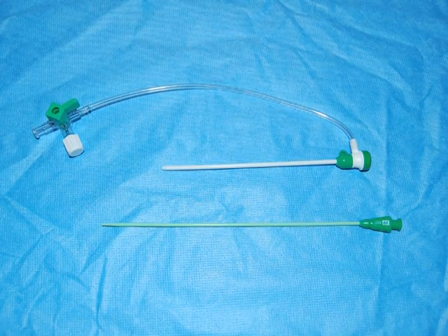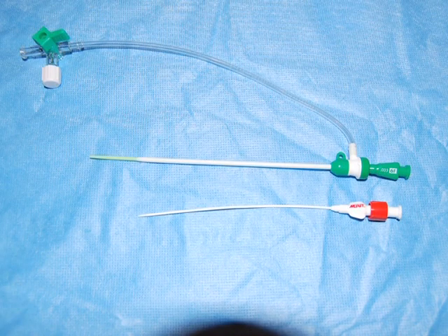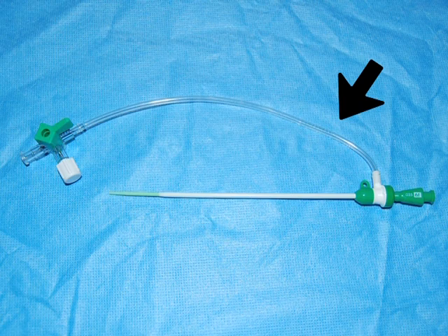The sheath comprises 3 major parts. It has a straight shaft through which the catheters pass, and on the end of this is the valve accepting the dilator. This dilator is manufactured with a central hole accommodating 0.038 inch guide wires, and in some cases the sheaths are designed specifically to accommodate only the micropuncture guide wires of 0.018 inches.